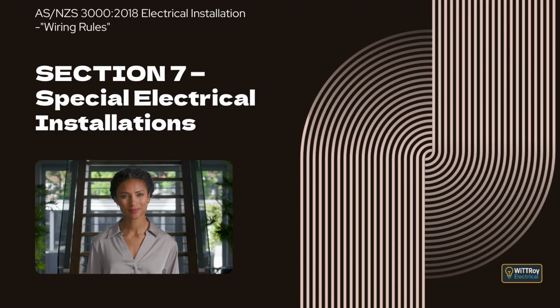Clause 7.2.5.4, Interposing switches for fire pumps and fire pump control equipment. This clause explains that no switch is permitted to be installed between a main switch and downstream switchboards that supply fire pumps and fire pump control equipment. The purpose is to avoid any unintended interruption of supply.